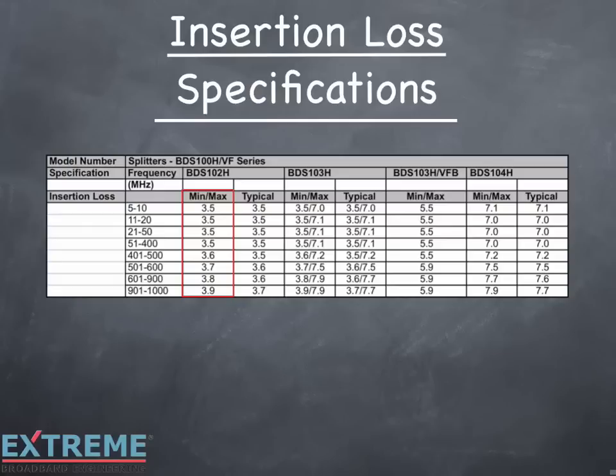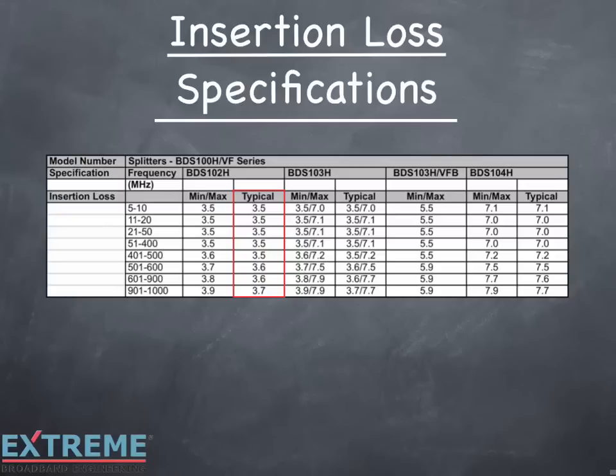The column next to that is labeled typical. These are the specification numbers that you would typically see from the majority of these devices in the field. Notice that the insertion loss at five megahertz is 3.5 dB and 3.7 dB at one gigahertz. Over the entire frequency band, it only loses two tenths of a dB. Most passive devices have minimal loss across the frequency band, and that is why we refer to them as a flat loss device.